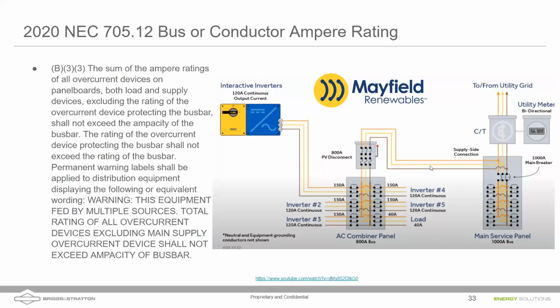So one thing you do, again, you have to put a sticker on there saying this is being fed by multiple sources, and essentially don't add anything in this panel if you're going to exceed the bus bar rating. This is common and usually done with inverter combiners as well. The idea here is that if there's power coming in, it's power flowing out, as long as you don't have any loads making that worst case scenario.